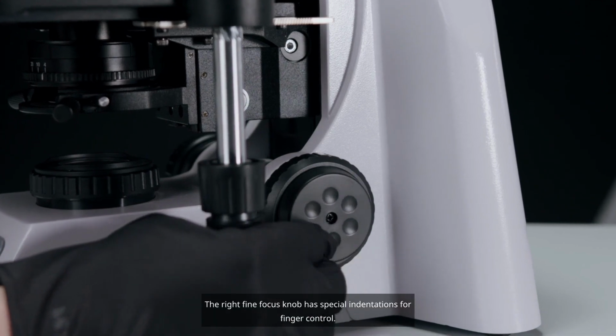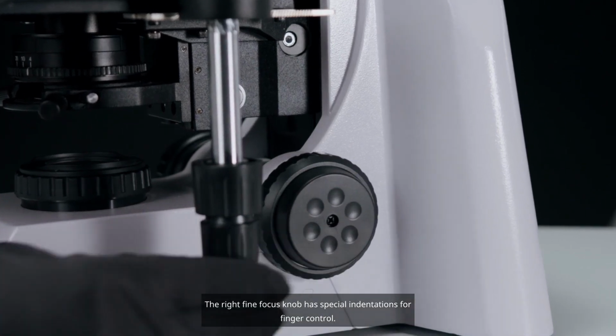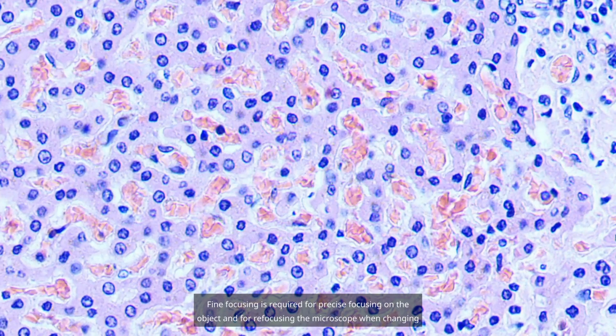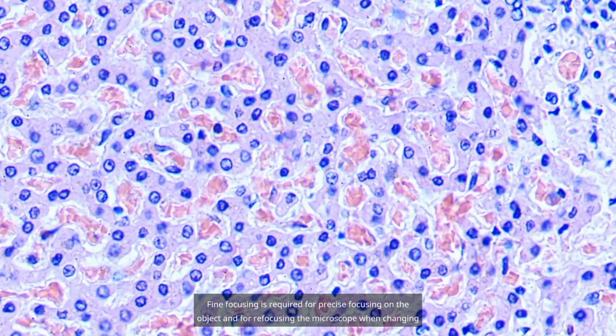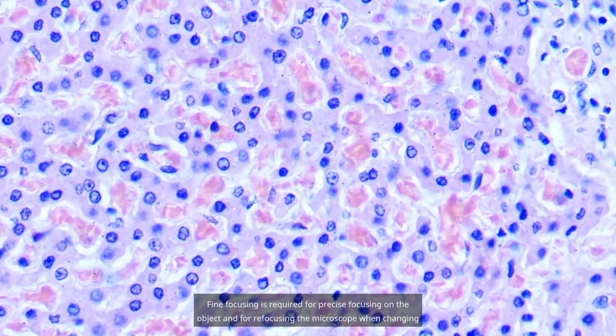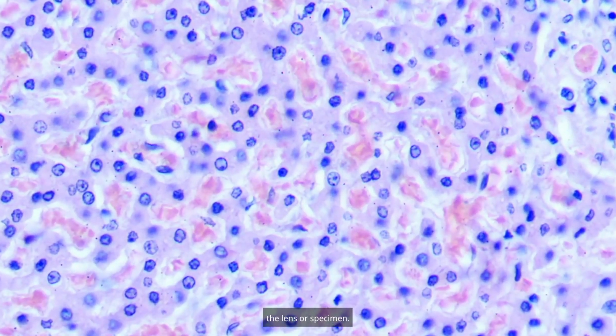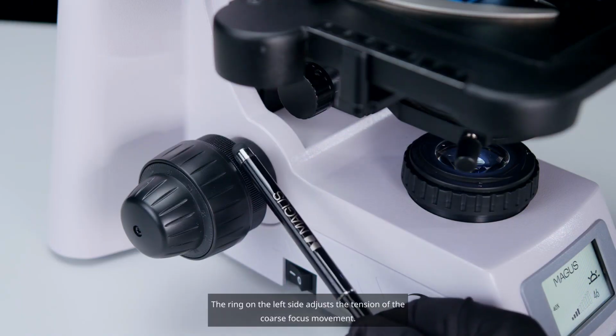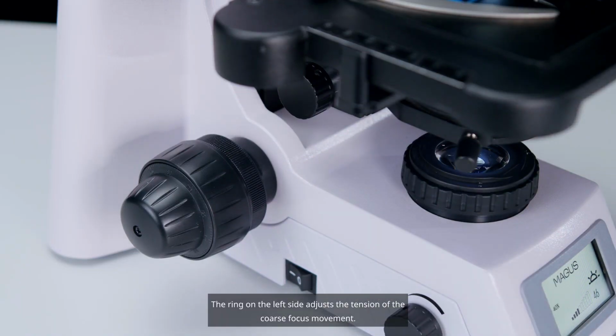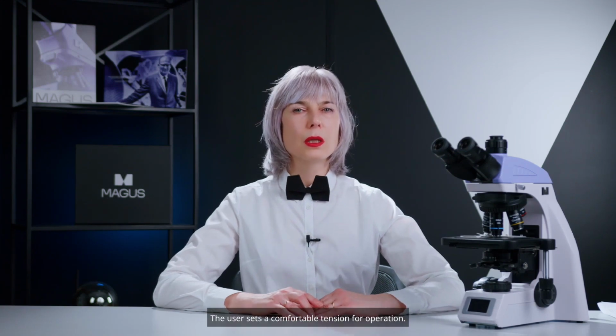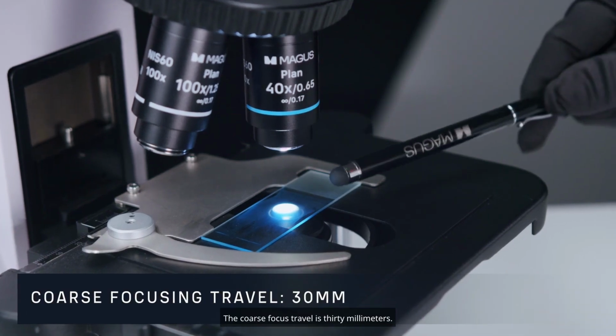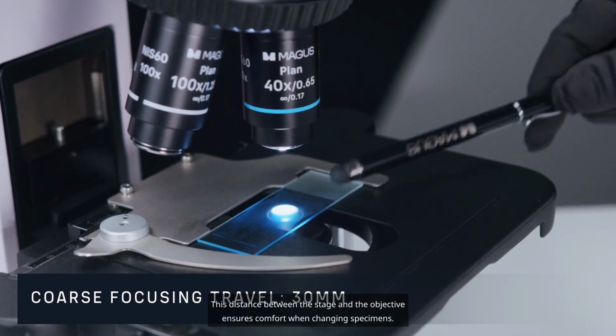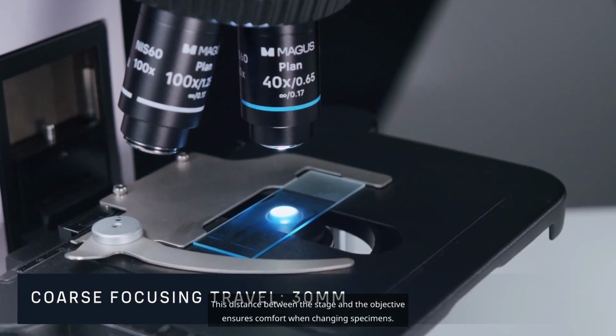The right fine focus knob has special indentations for finger control. Fine focusing is required for precise focusing on the object and for refocusing the microscope when changing the lens or specimen. The ring on the left side adjusts the tension of the coarse focus movement. The user sets a comfortable tension for operation. The coarse focus travel is 30 millimeters. This distance between the stage and the objective ensures comfort when changing specimens.